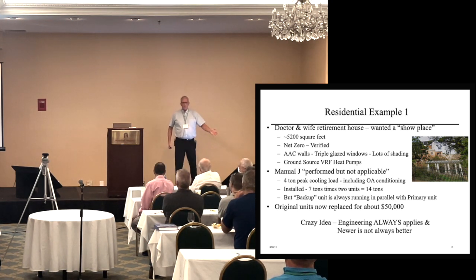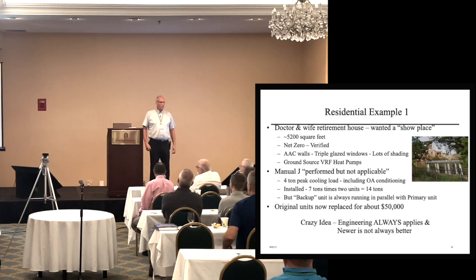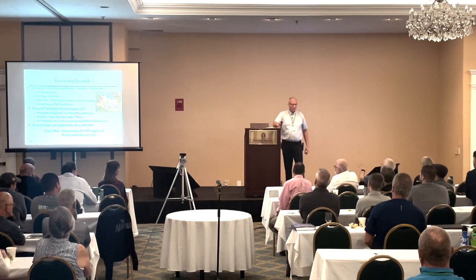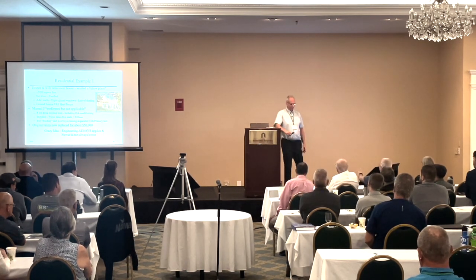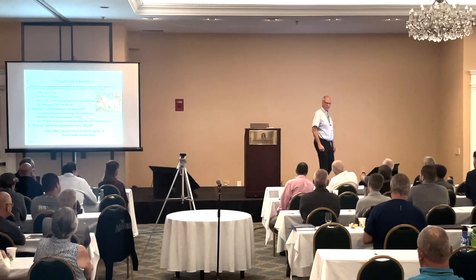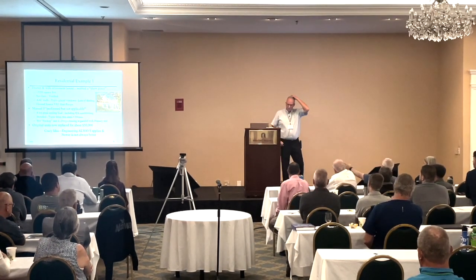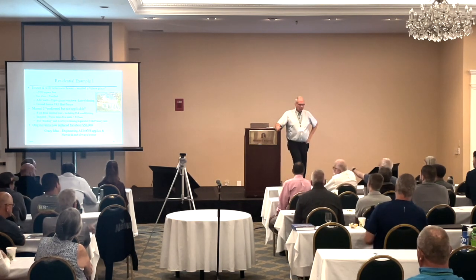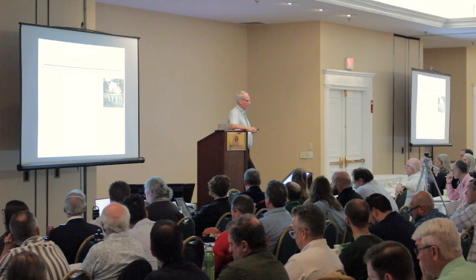The original units have now been replaced at a mere cost of about $50,000. So they replaced them for 50 grand. Did they put the same things in? No. What did they do instead in this situation? This is a really nasty, tricky thing. Not a good idea to have all those little units going to a single outdoor unit, much less two. Bad, bad, bad. But what did they do instead that would be slightly less bad here to fix this?